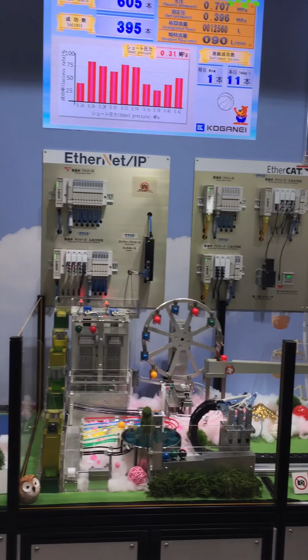Once you connect to the IO-Link master, all you do is take your computer and type in your 192 dot whatever address on the web. It'll find that master, and it'll give you full diagnostics as to what's happening with it. So when they talk about the Internet of Things, that's one of the ways to get into it. But the whole system works with every product, because IO-Link is an industrial standard. And that's a real advantage.